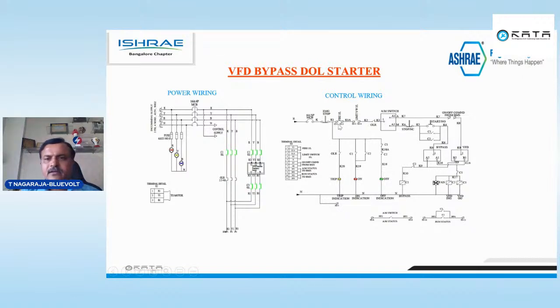So these are all the control circuits we are using: fire interlock, limit switches, auto manual, and your overload is also there. In the VFD bypass, the fan and everything will be there. So fire interlock, limit switch, on off command. Whatever we give in the same DOL starter, we can also provide in the VFD bypass, we can give the provisions.